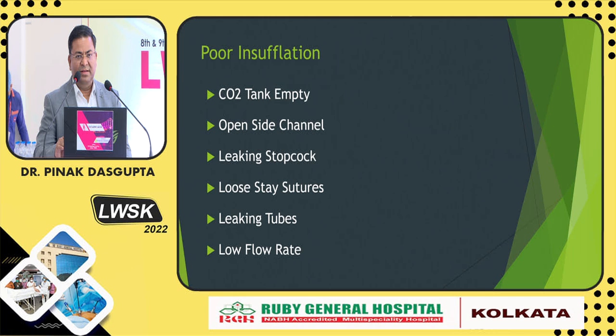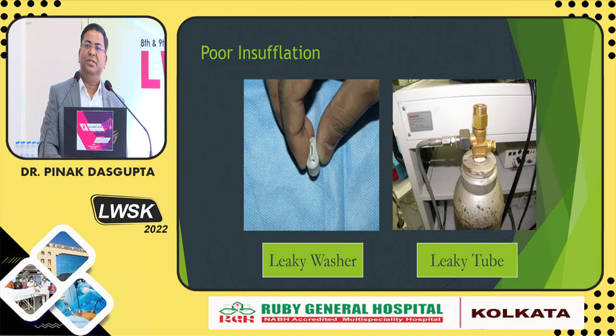Check whether the carbon dioxide tank is full or not. If any side channels are open in the trocars, if stopcocks are leaking, or if there is a loose stay suture, the gas may leak from the periphery of the trocars. If there is any tube leak, that can also be picked up with a high flow rate but low pressure inside.